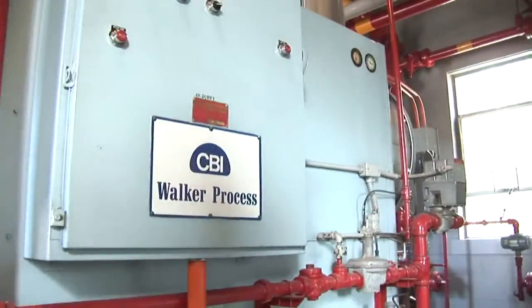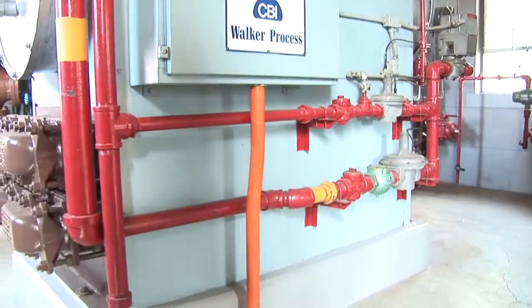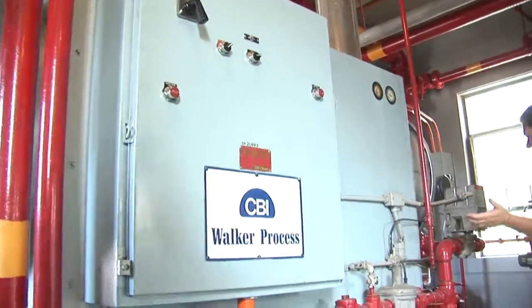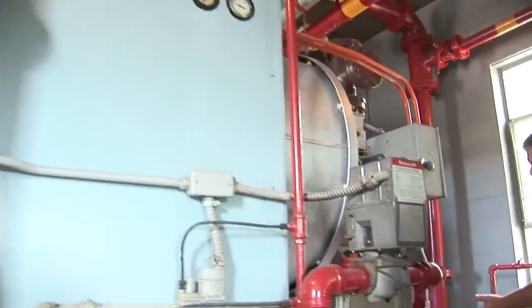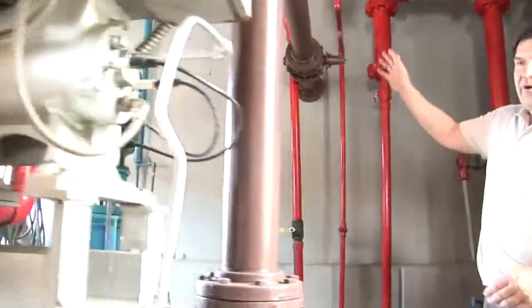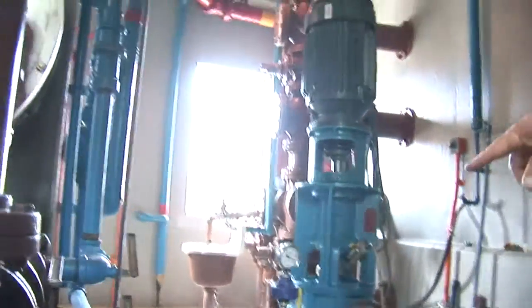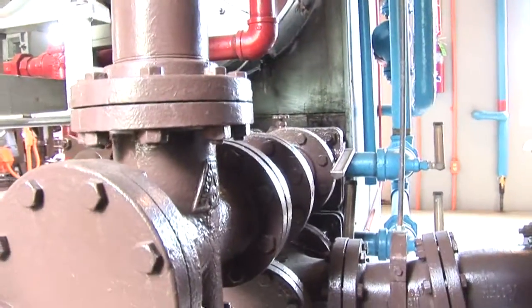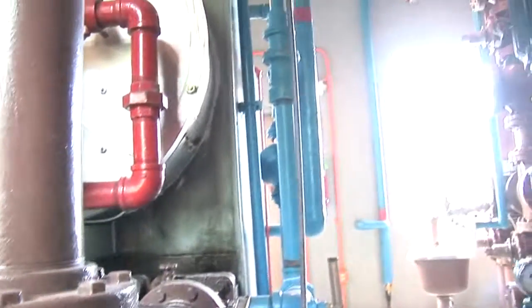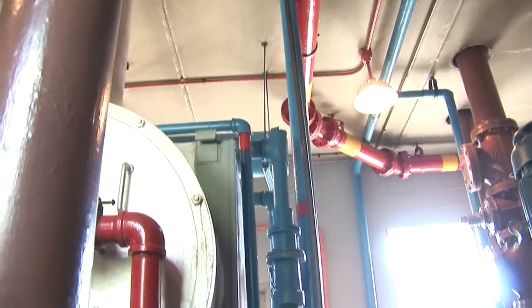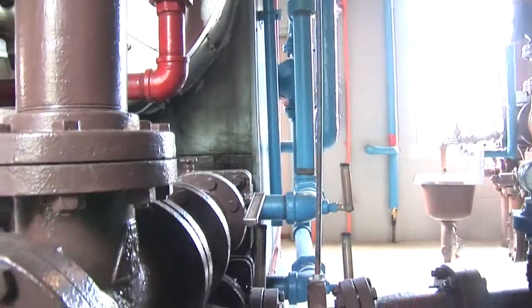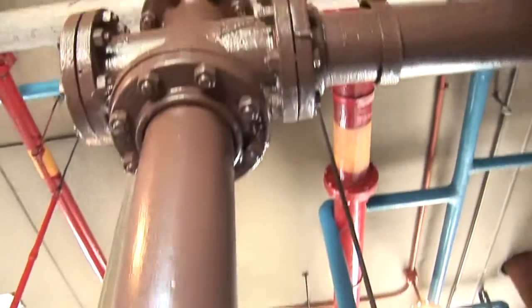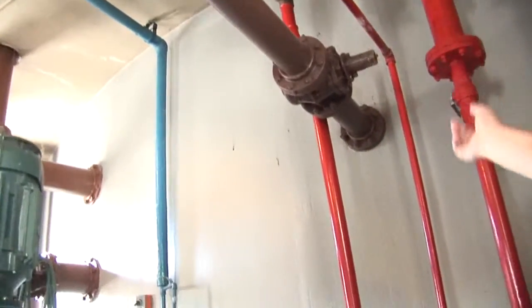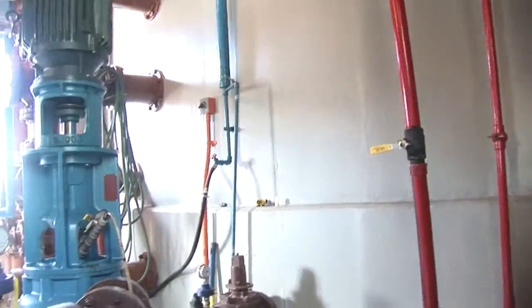We have a boiler. The boiler is currently operating, but it's not fired up right now. It's maintaining the temperature of about 95 degrees. We have a heat exchanger. The brown pipes here represent the draw from the digester, which comes into the boiler through the heat exchanger. The blue pipes are the water jacket from the boiler bringing hot water into the sludge heat exchanger. Then the sludge is heated up to 95 degrees and returned back to the digester. This is a continuous loop system to maintain the digester temperature.